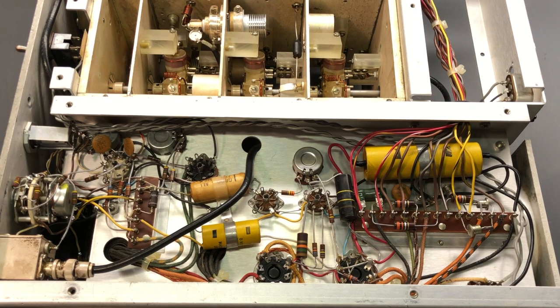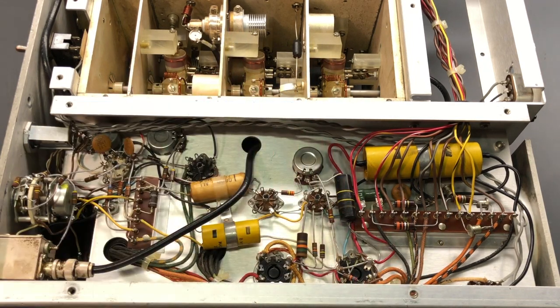ohm resistors. So there's one resistor per RF power tube, and they're in the filament circuit. They're in series with the filament. So the power transformer has 3 dedicated windings for the filaments, one winding per RF power tube. So I'll go ahead and change all 3 of these resistors. They're certainly easy to do, so we'll get that taken care of.